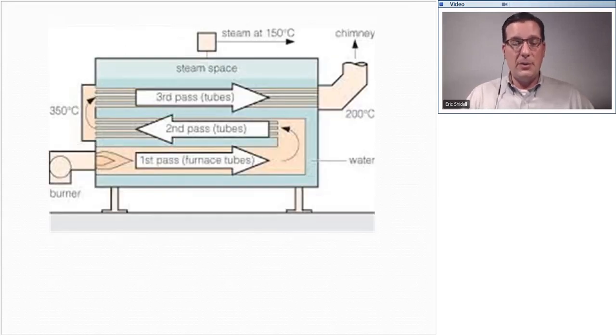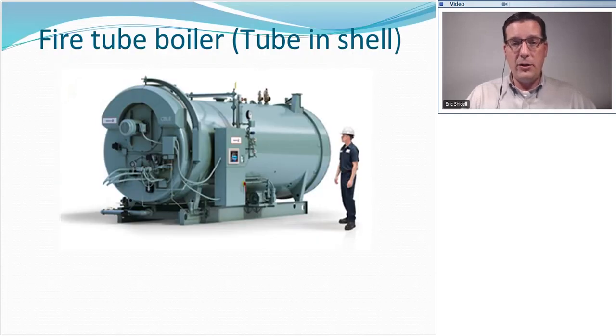Here's another example of what one would look like from the side. Fire coming in here, going through the tubes, up the flue. Meanwhile, there's water all around. Shell and tube boilers can be steam or they can be hot water. If they're steam, they're not going to be full all the way to the top. There's going to be space in the top for steam generation. If you are a steam boiler, you are going to have a sight glass along the side. And here we have some of that sight glass apparatus that's a little hard to see because it's partially hidden by the controls, but this looks like it could be a steam boiler. A hot water boiler is not going to have a sight glass on the side because it's all the way full of water.